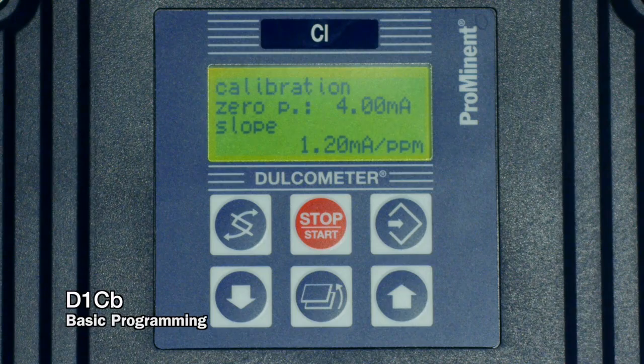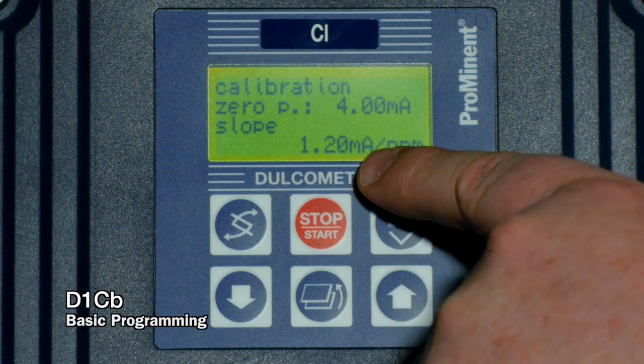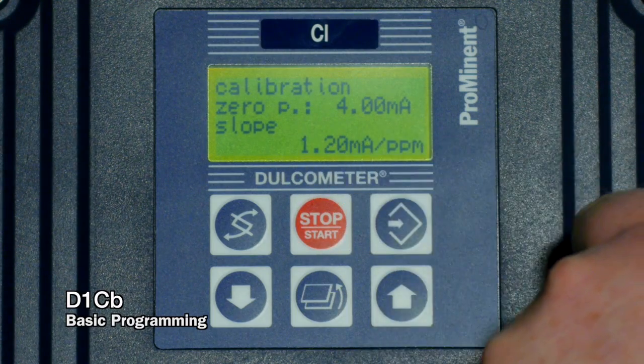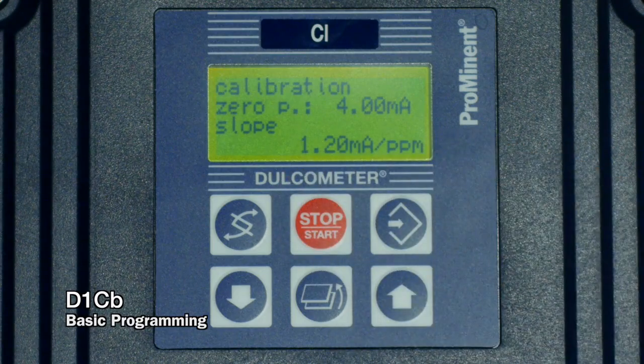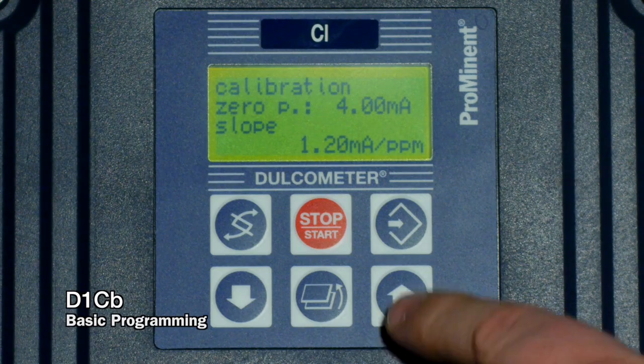It tells you what the resulting slope is of your calculation. Here it tells us 1.2 milliamps per part per million. That's the default slope value for a 10 part per million sensor. It will accept the slope until we go down to 25% of that initial starting slope. So 0.30 would be acceptable. If the resulting calculated slope is below that, it will not accept the calibration.